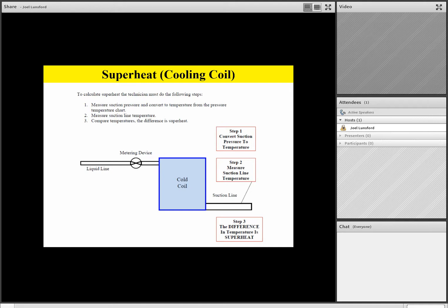Now, to calculate superheat, the first thing we're going to do is convert suction pressure to temperature off of our pressure temperature chart, just like we did in practice a few moments ago. Step number 2, we're going to measure the suction line temperature leaving that cold coil. Step number 3, we'll find the difference in temperature between step number 1 and step number 2, and the difference is our superheat level. And remember, team, looking at the condition of the coil, flooded, starved, or normal, will help us determine where the refrigerant is in the refrigeration cycle, and it'll also help us be a better diagnostic technician.